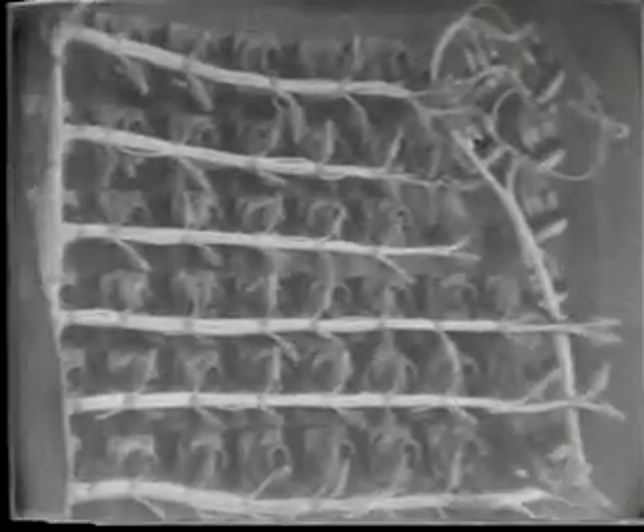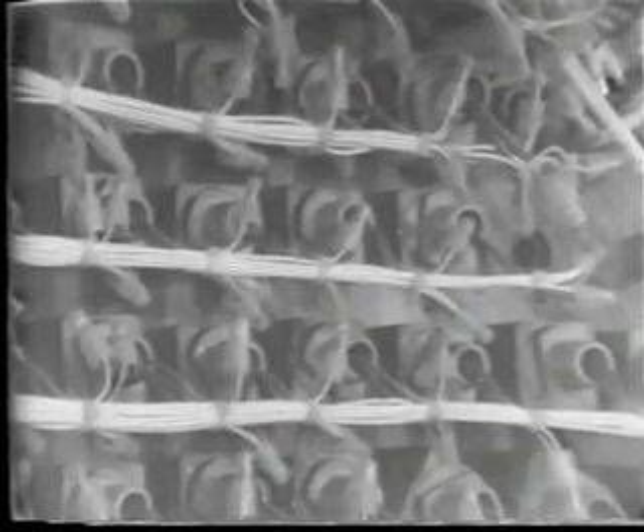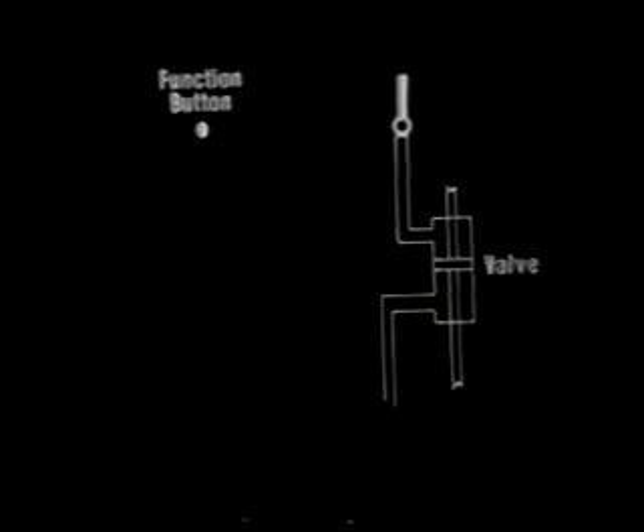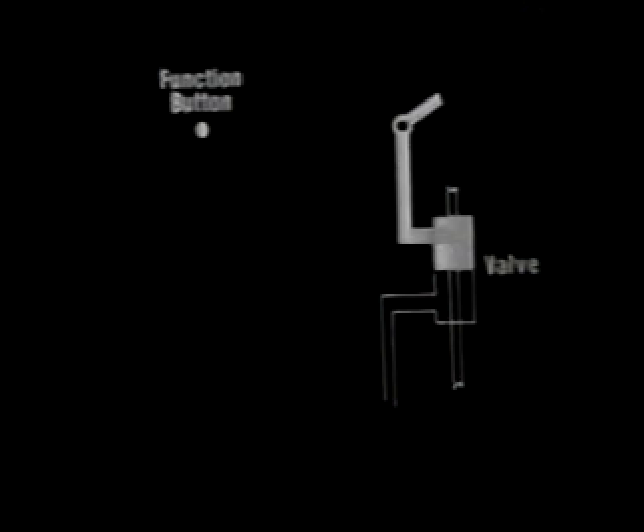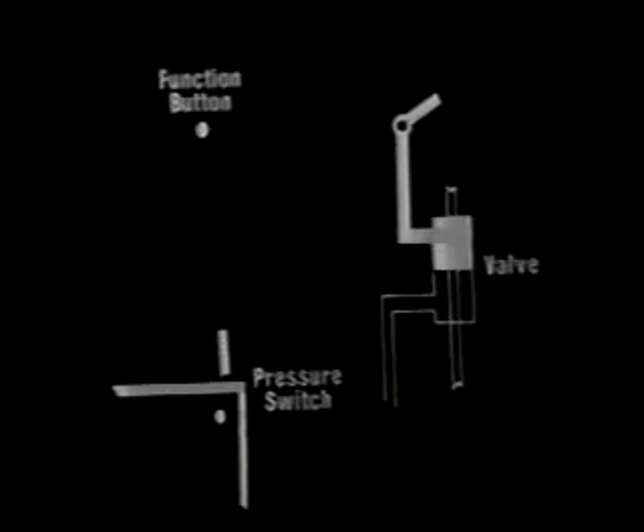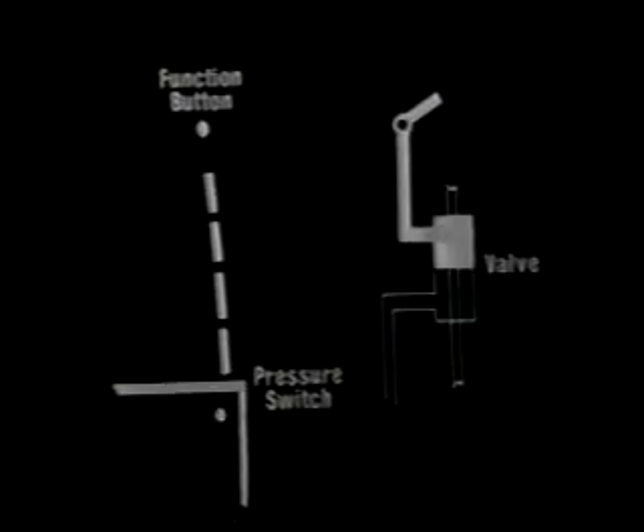One of the purposes is to operate the indicating lights on the remote panels. These pressure switches are activated by the pilot pressure for the various functions. When a function button is pushed and the solenoids cause the function on the front of the hydraulic control manifold to shift, pilot pressure is placed on that function's valves. This pilot pressure activates the corresponding pressure switch in the junction box, and in doing so turns on the indicating light on the remote panels. These pressure switches are preset at the factory.